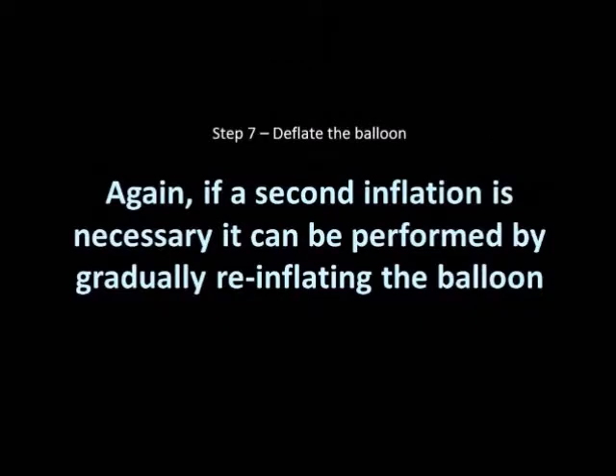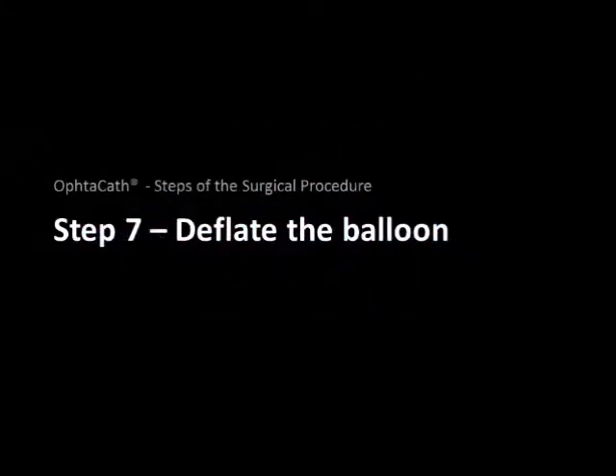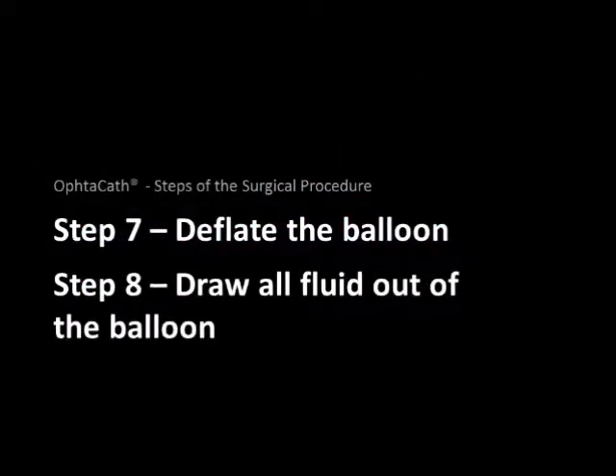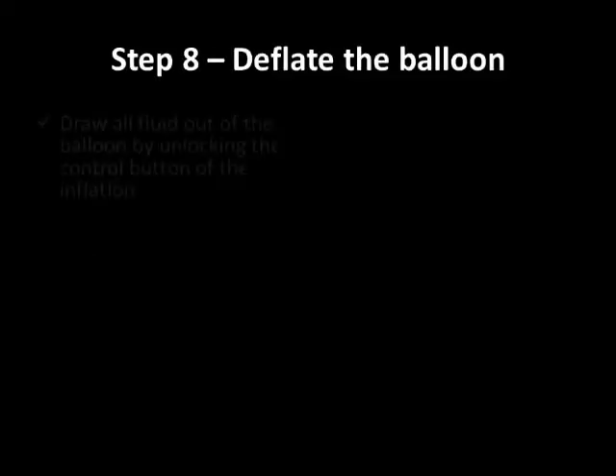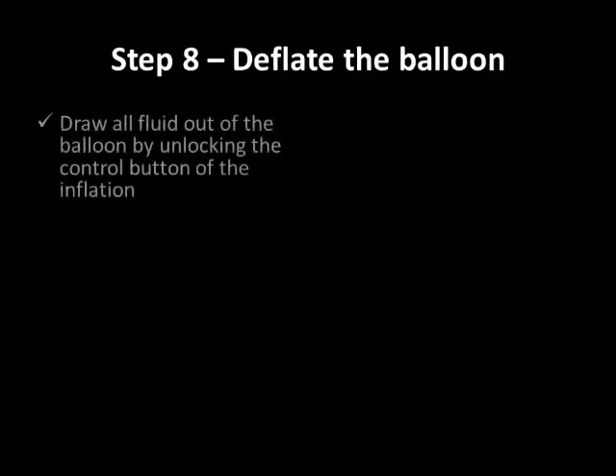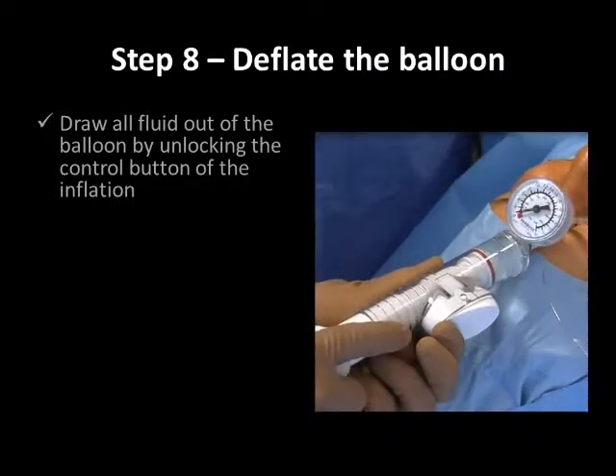Step 7, deflate the balloon completely. Again, at this point, if a second inflation is necessary, it can be performed by gradually reinflating the balloon to 8 atmospheres, this time for 40 seconds, then deflating the balloon again. Step 8. Now the balloon is deflated, but to ensure the balloon is as small as possible, the surgeon must draw all fluid out of the balloon.